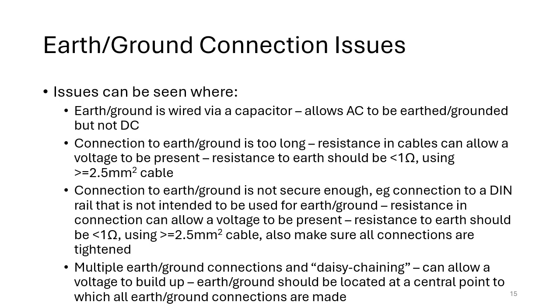If the connection to the earth or ground is not secure enough, for example, you might have a connection to a DIN rail that's not intended to be used for earth or ground. That can be because, again, the resistance to the earth connection is too high and allows a voltage to be present. So you need to make sure, again, that resistance to earth should be very low, using a specific thickness of cable, minimum 2.5 millimeters squared cross-sectional area. And again, make sure all the connections are tightened.